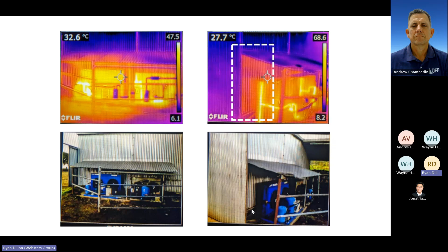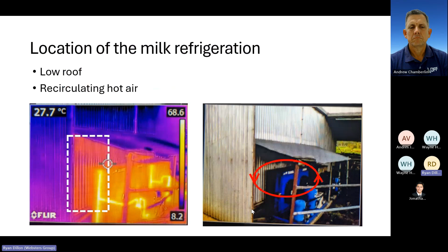And while to the untrained eye, that might not seem like much, just in that picture there, what we can actually see is that the air rejected that moves out to the right-hand side is hitting the top of that roof. And this is this little red chart on the picture on the right-hand side, where we see by the shape of the roof, some of the hot air rejected is actually recirculating and being sucked in by the back of this condenser. So what does that mean?